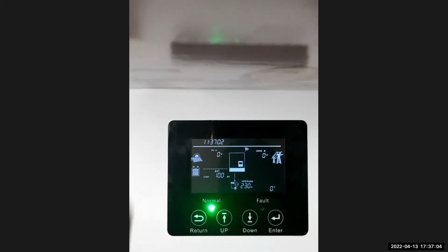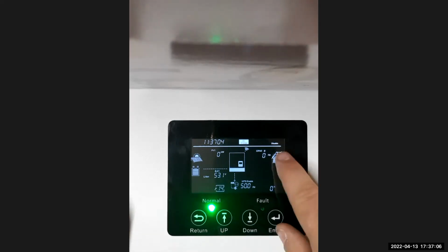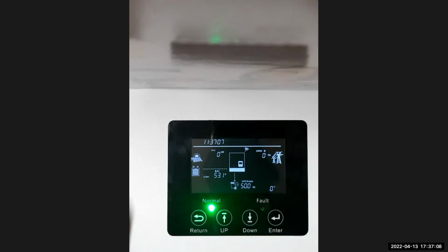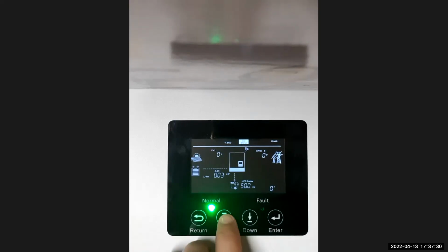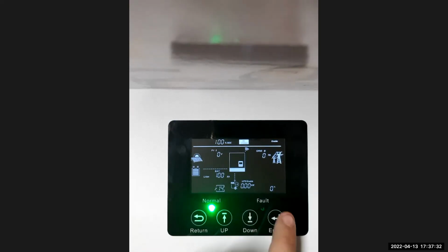So it works the same as the app. You can disable it. You can see in the corner there's a flashing disable. Then you know your AC charge won't be able to charge your system. But if you want it to charge your system, say it's a cloudy day, you can enable it. And I always put it around 30 to 40 amps maximum that it will charge from the grid. Then SOC is where it must charge up to. So in this case, I would just say 100%. So it will charge it till 100%.